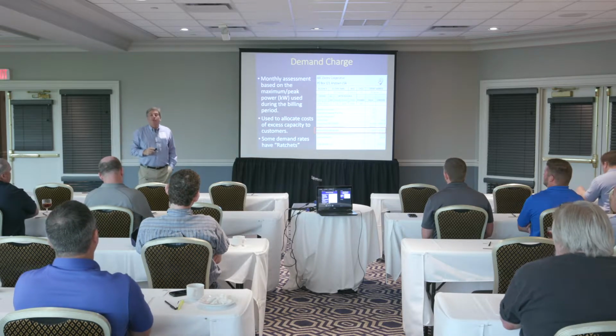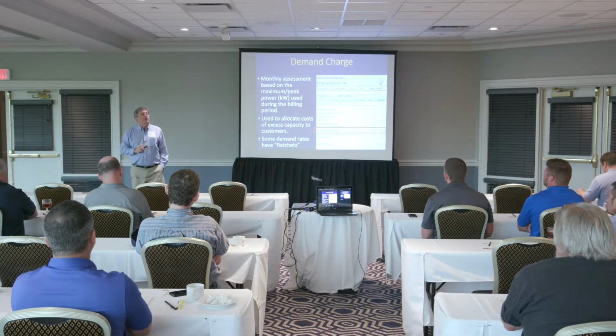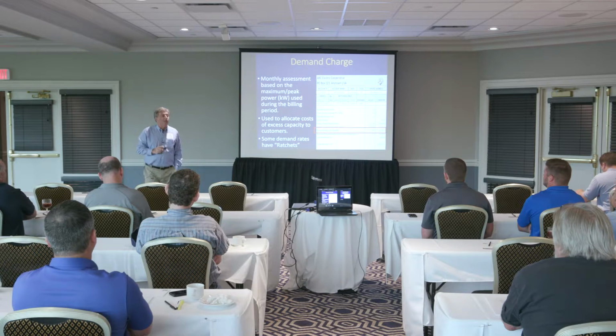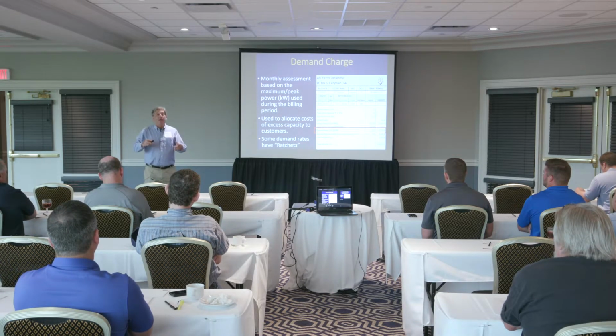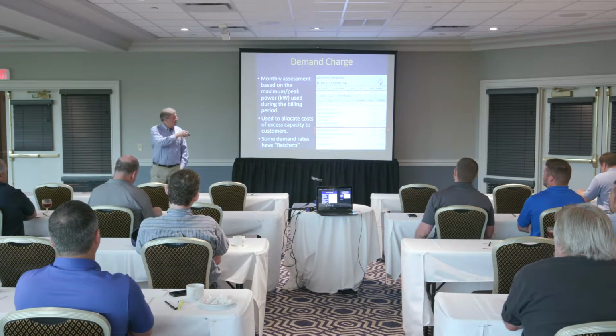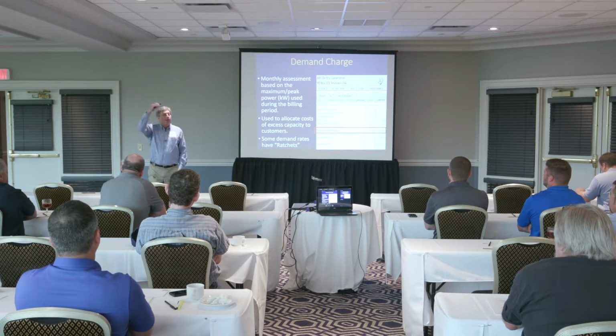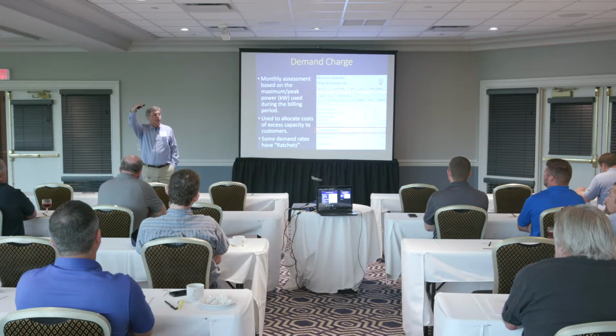The jargon terms we use in the industry are coincident peak or non-coincident peak. If I'm billed on coincident peak demand, that means that number came from the amount my plant had on at the time the co-op peak happened, or Hoosier peak. If it's non-coincident peak they're billing on, it's your plant maximum.